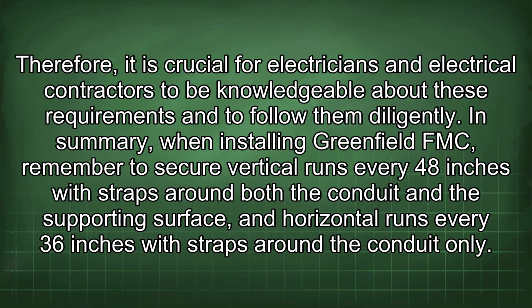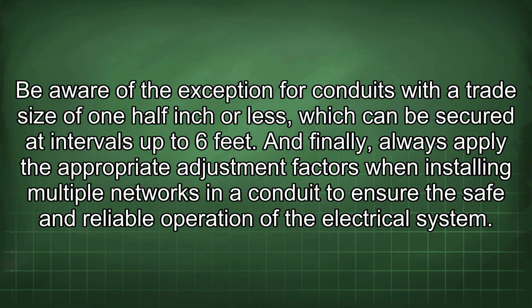In summary, when installing Greenfield FMC, remember to secure vertical runs every 48 inches with straps around both the conduit and the supporting surface, and horizontal runs every 36 inches with straps around the conduit only. Be aware of the exception for conduits with a trade size of 1/2 inch or less, which can be secured at intervals up to 6 feet.